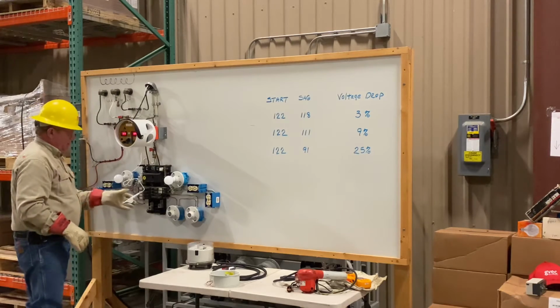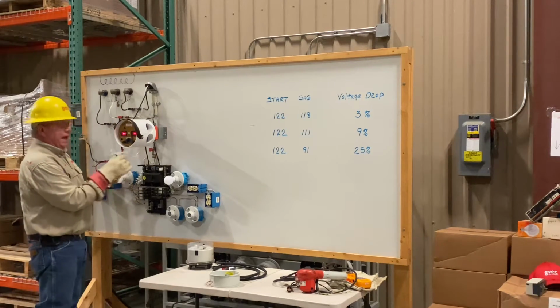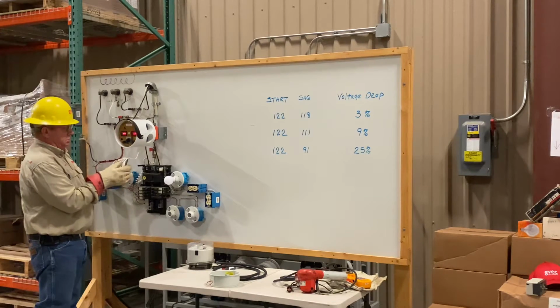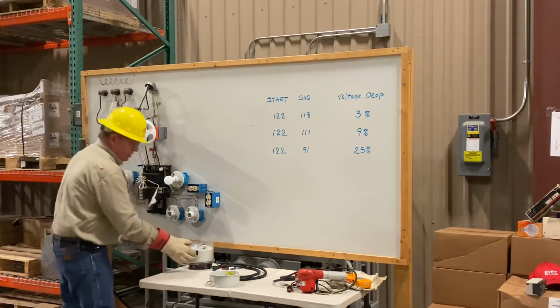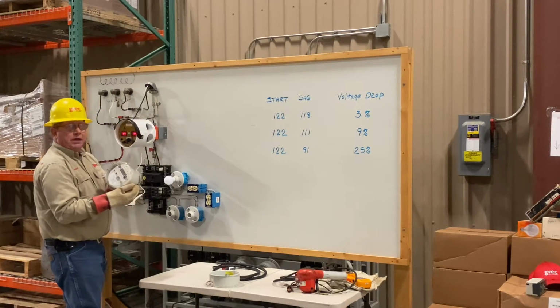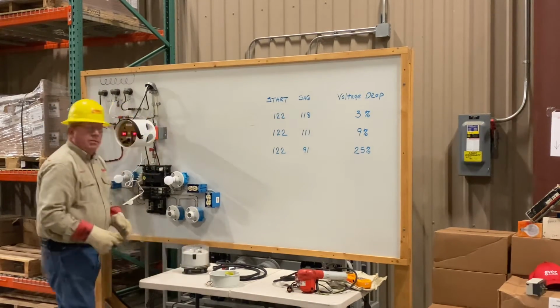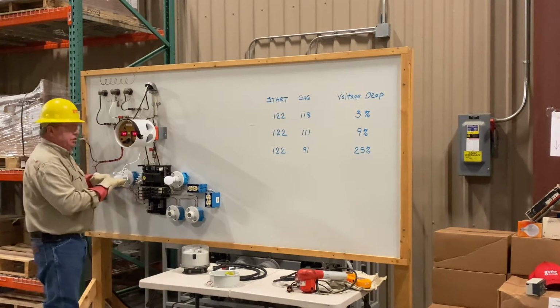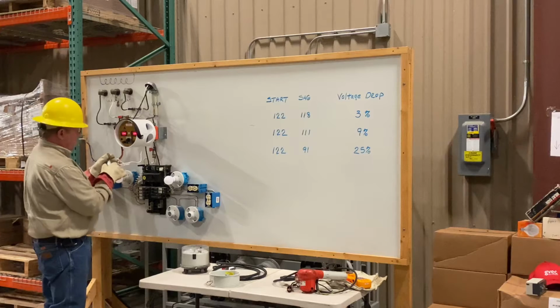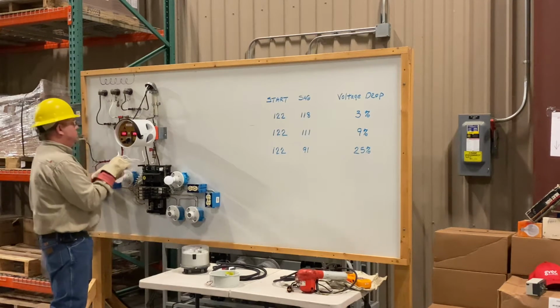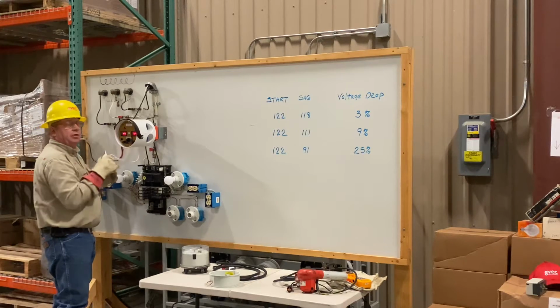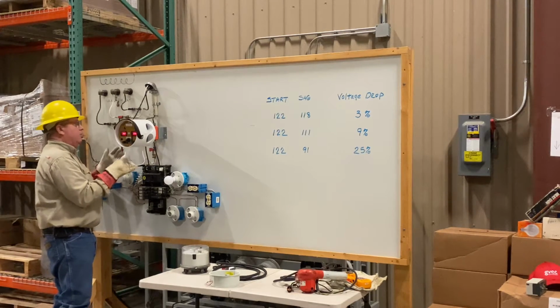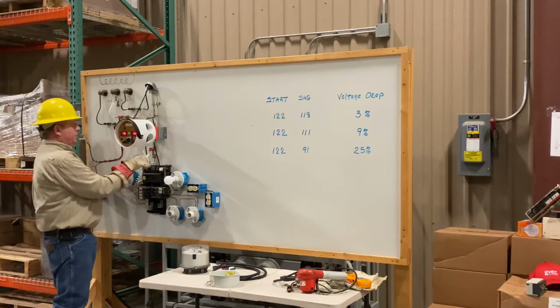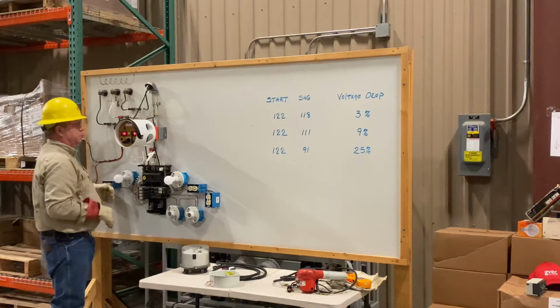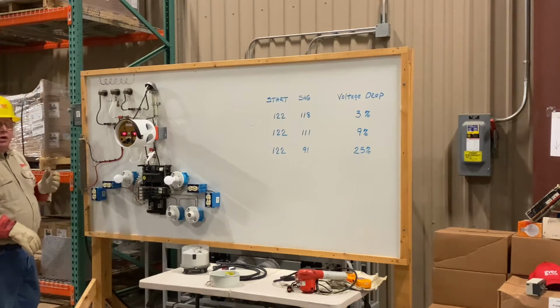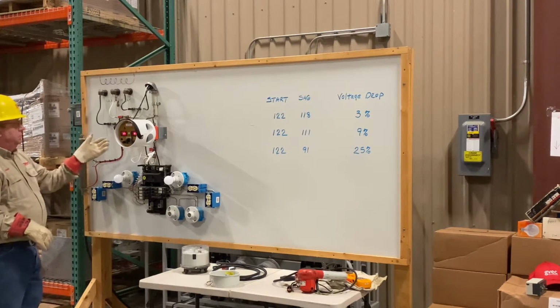The most important thing, just like a PMI recorder, is we have to attach the neutral. The meter we have doesn't have a neutral tag on it, so whether we're installing a PMI recorder or a Super Beast, we have to make a neutral connection. They're telling you, Super Beast people, stick this back in the meter socket and grab that neutral bar. Well, that's what we're going to do. I don't have a bare neutral back there, so I'm going to grab it right here. And we can see that unloaded, we have a balanced voltage.